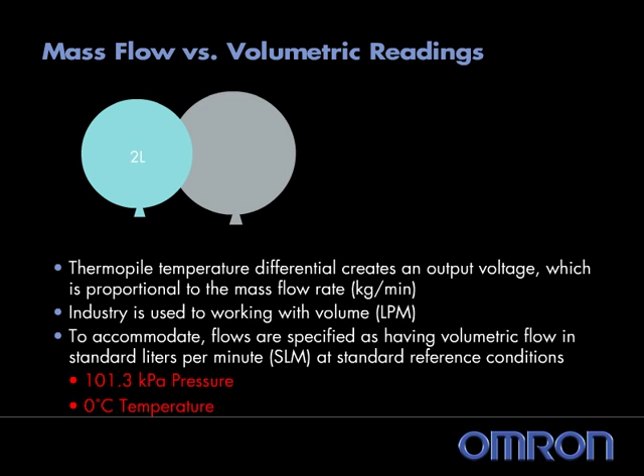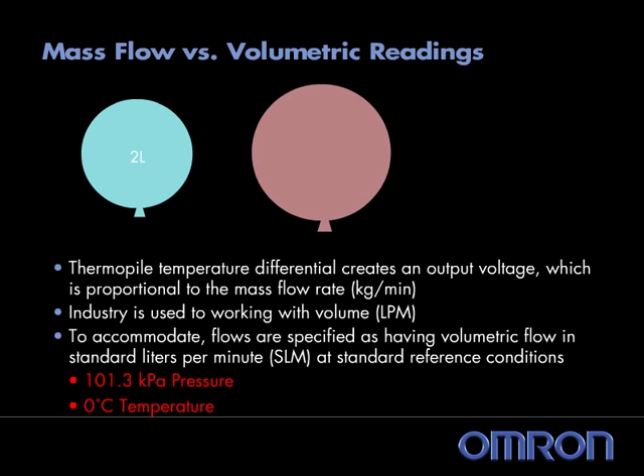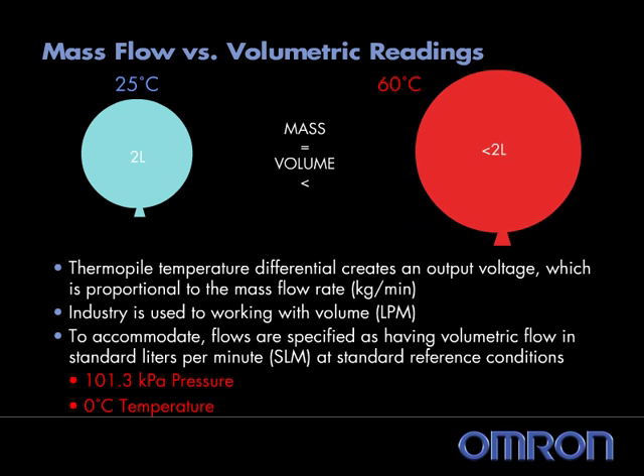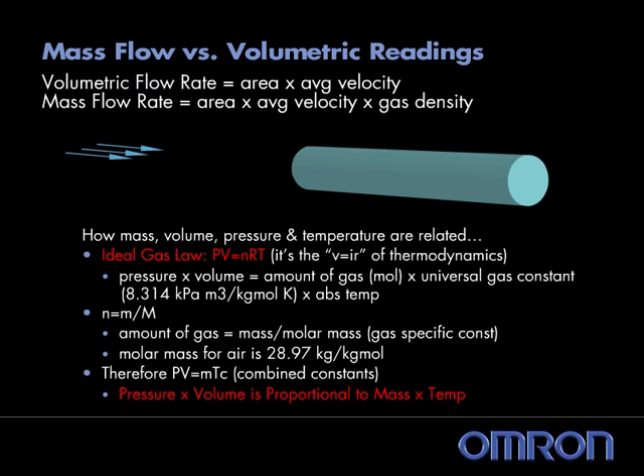While these are mass flow sensors, the OMRON data sheets show flow ranges in liters per minute, a volumetric unit. Because the industry is more familiar with sizing flow sensors volumetrically, the mass flow ratings have been converted to volumetric flows at standard conditions.